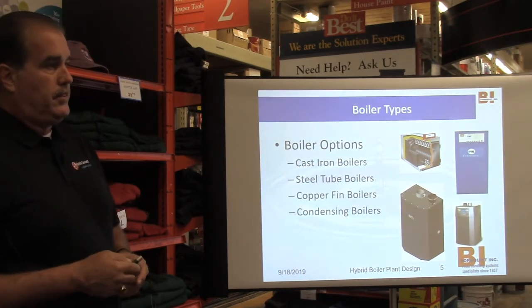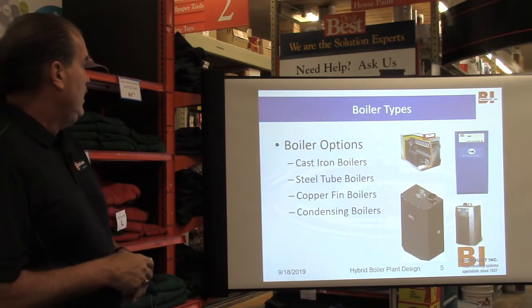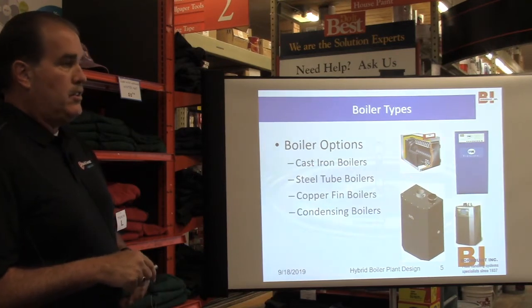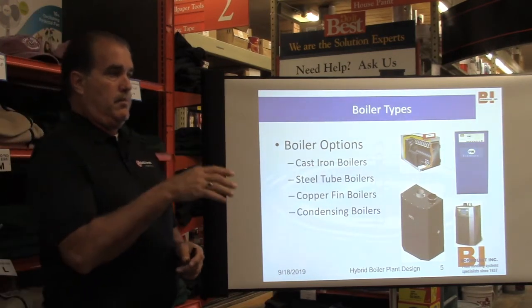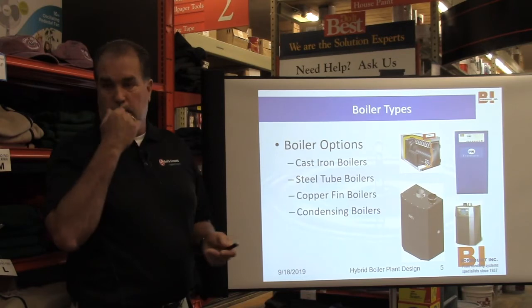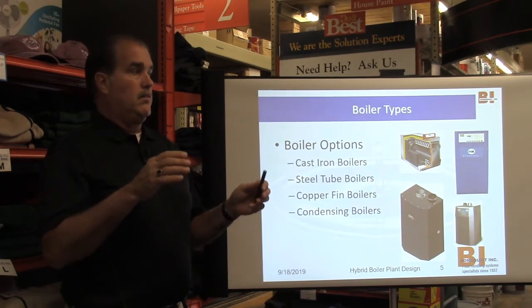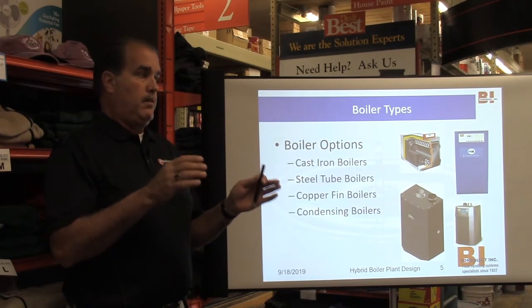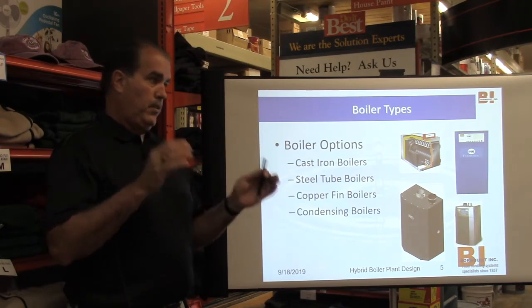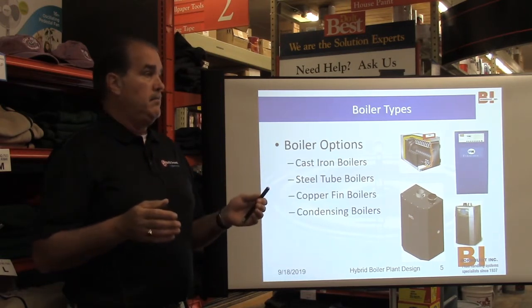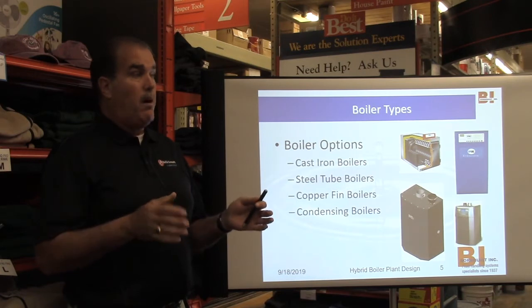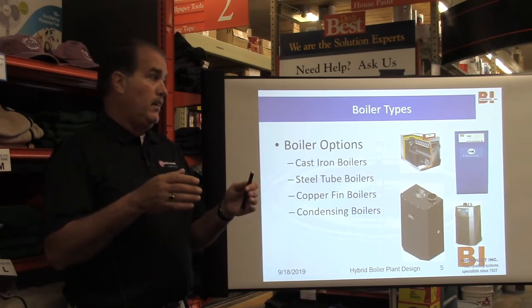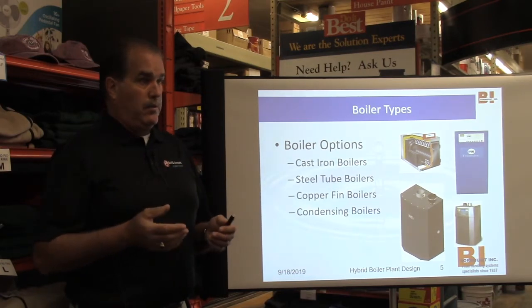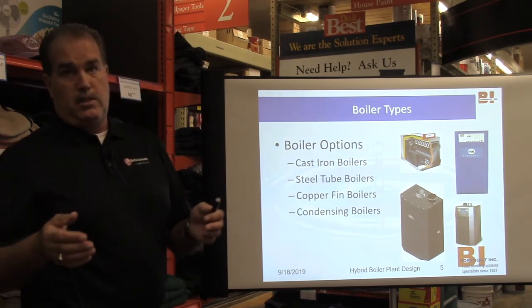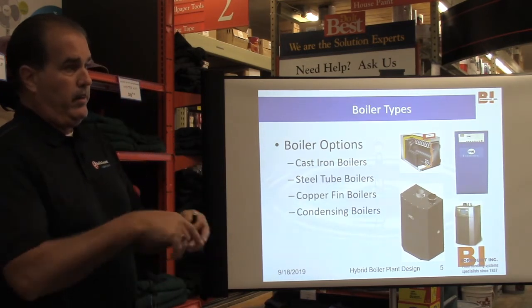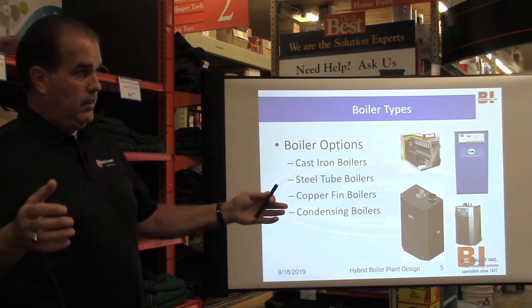But they do come in different styles, okay? Some of them are cast iron. These are your old cast iron steam boilers. Even water boilers you can get in cast iron. And these are probably the type of equipment that was put in a building that was built 40 or 50 years ago. They still make them. They've gotten smaller, I will say that. If you're going to get a cast iron boiler replaced, odds are it's going to be considerably smaller. They call it a footprint. It will have a smaller footprint than the one that was there.